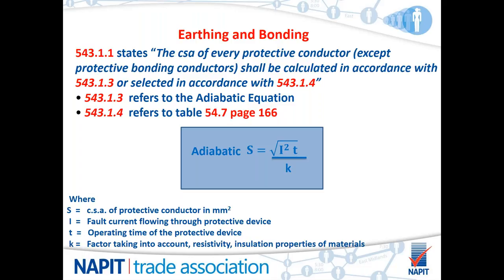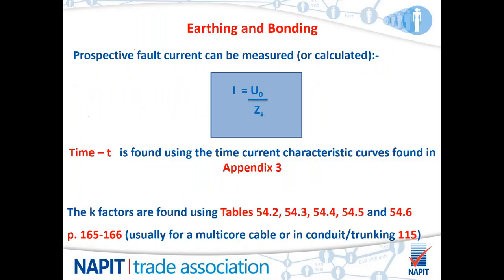S is the cross-sectional area of protective conductor required in millimetre squared. I is the fault current that will flow through the protective device when the fault occurs. T is the operating time of that protective device. This is not the maximum operating time, this is the actual operating time. And K is a factor given to the protective conductor, which takes into account its resistivity, the insulation properties around that material.